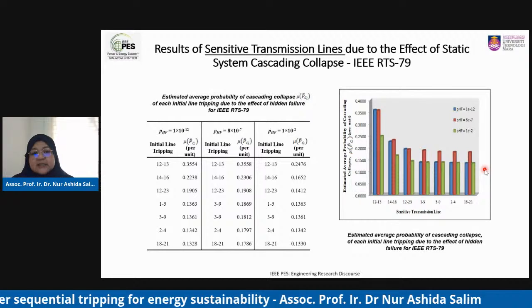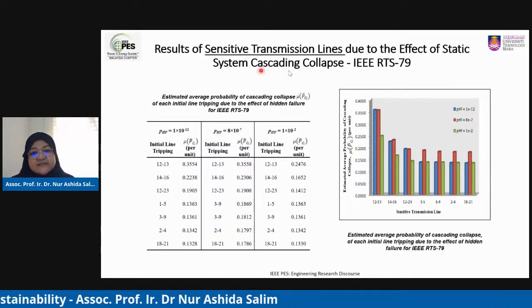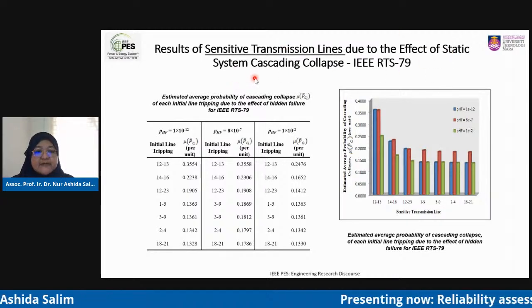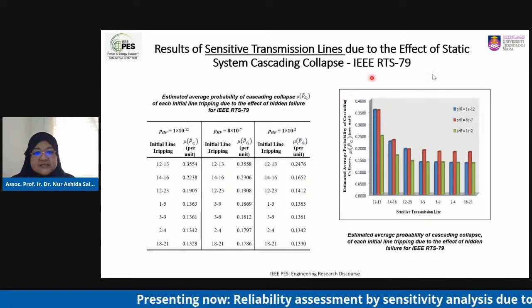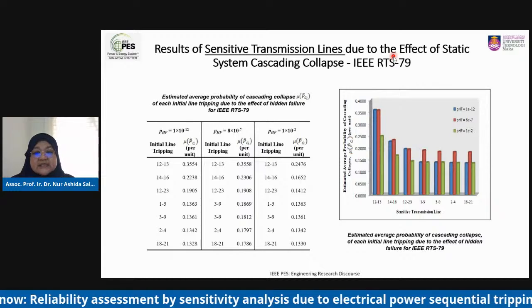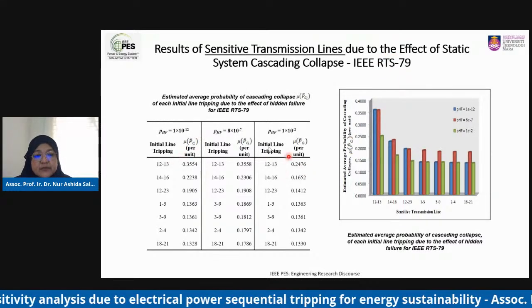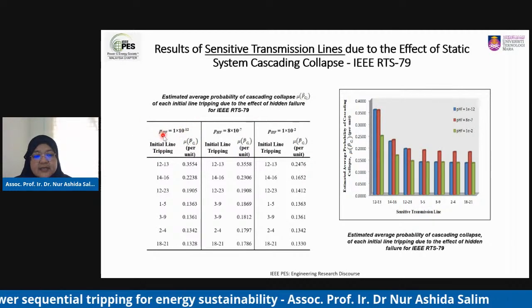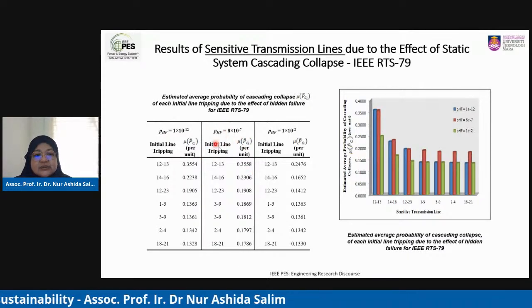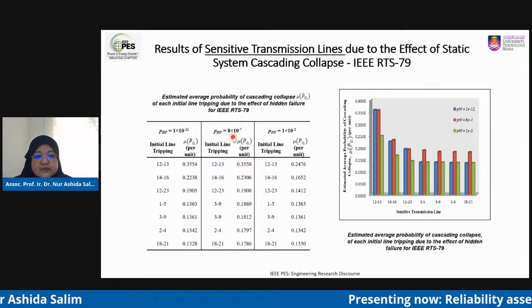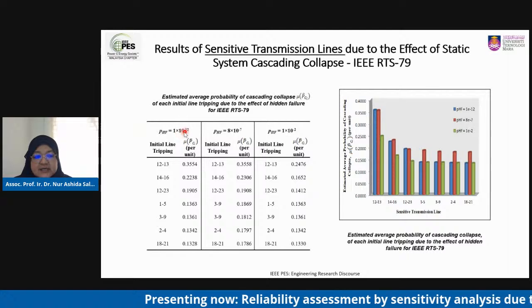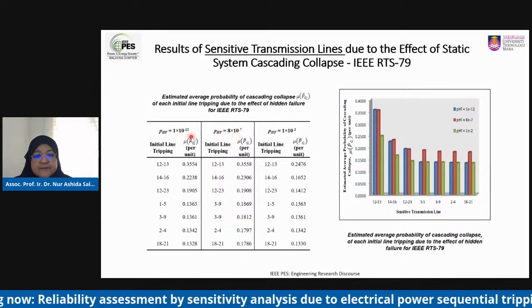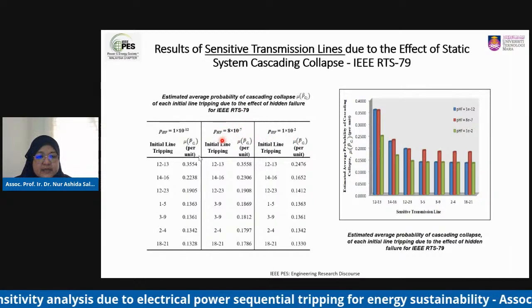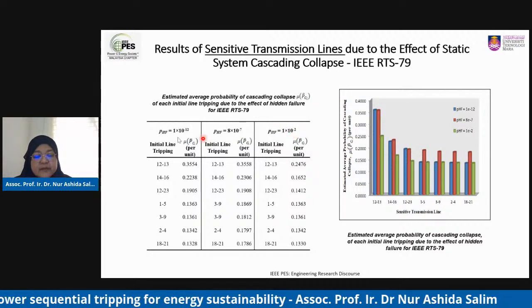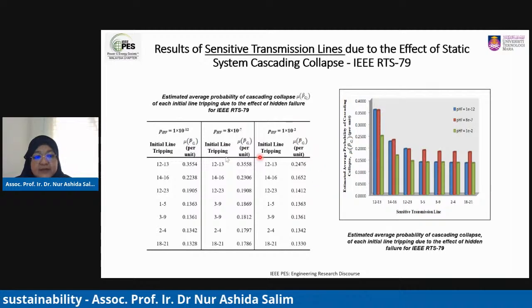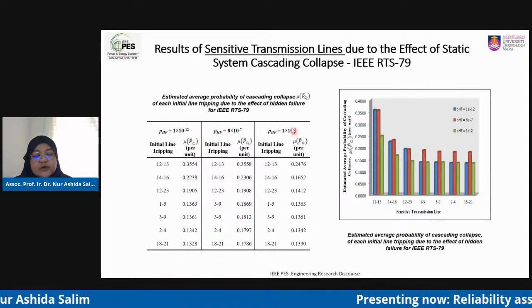This is the results I have gathered for the sensitive transmission line, due to static system cascading collapse, only for transmission line tripping. This is for the 1979 test system with 38 transmission lines. In the table, I've tabulated three different values of the hidden failure probability. In the middle is the probability calculated based on the NERC report, which is 8 times 10 to the power of negative 7. On the left, I selected a lower value of PHF compared to the NERC report, and on the right a higher value of PHF. We want to monitor the different effects on the probability of system collapse if the PHF value differs.